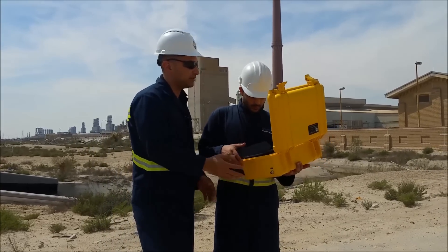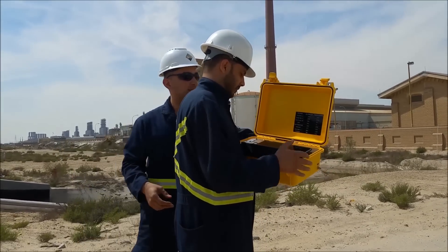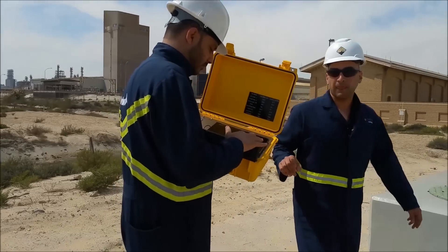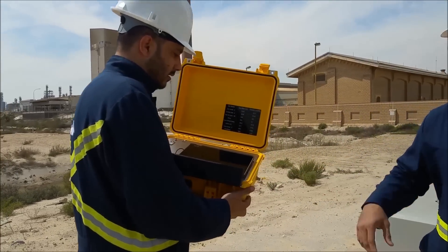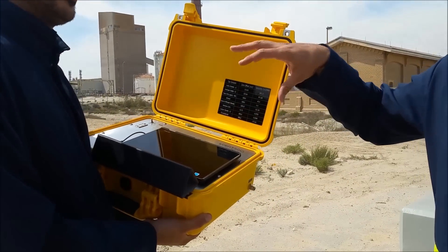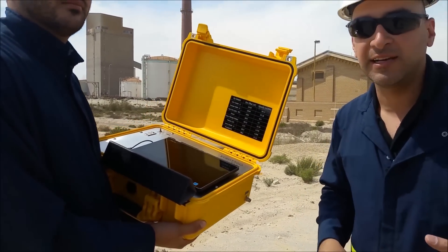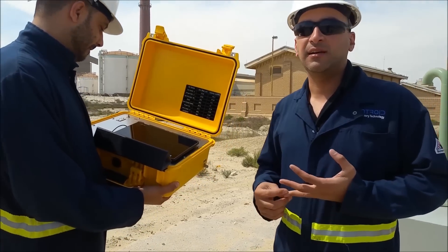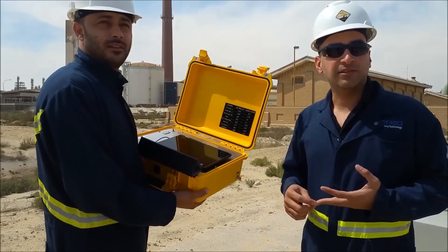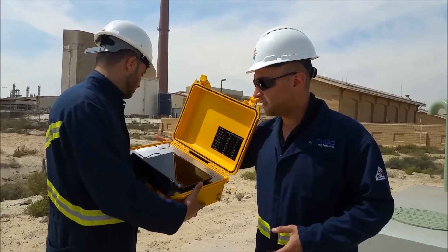The sample is pulled in from this side and there is an internal pump which will take the sample in and pass it over those sensors, which include photoionization, NDIR, and electrochemical cells. They will make a measurement and the exhaust goes out here.